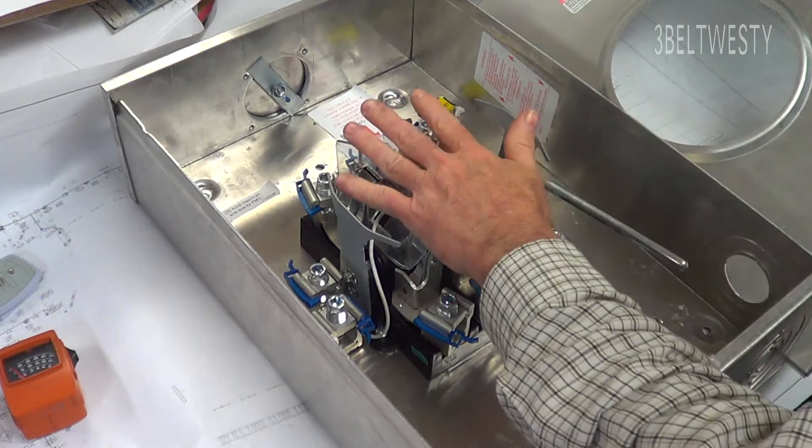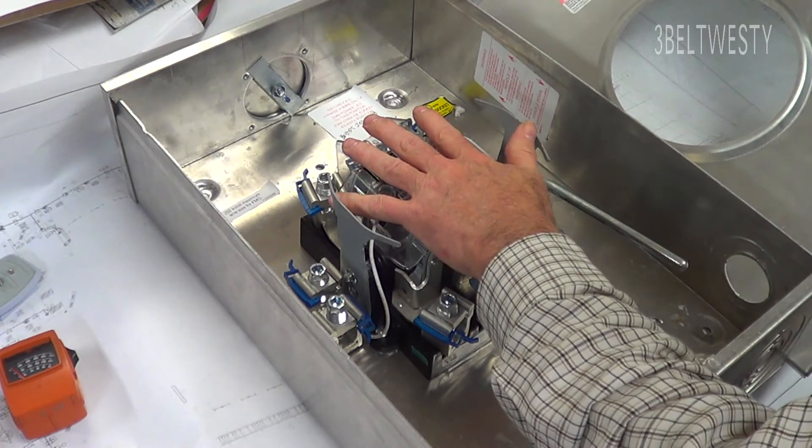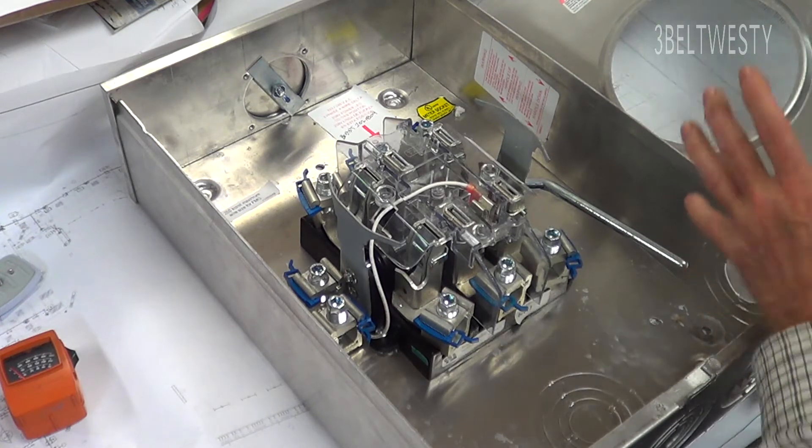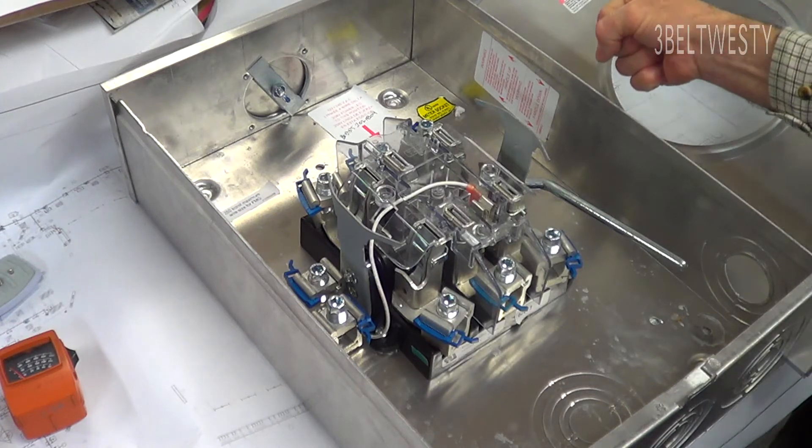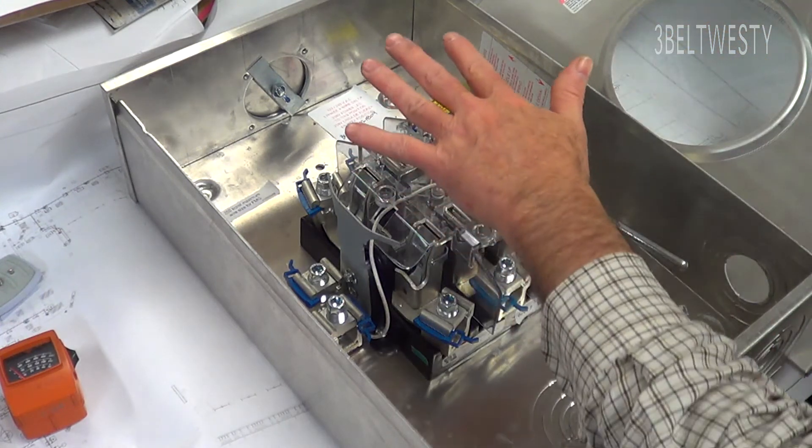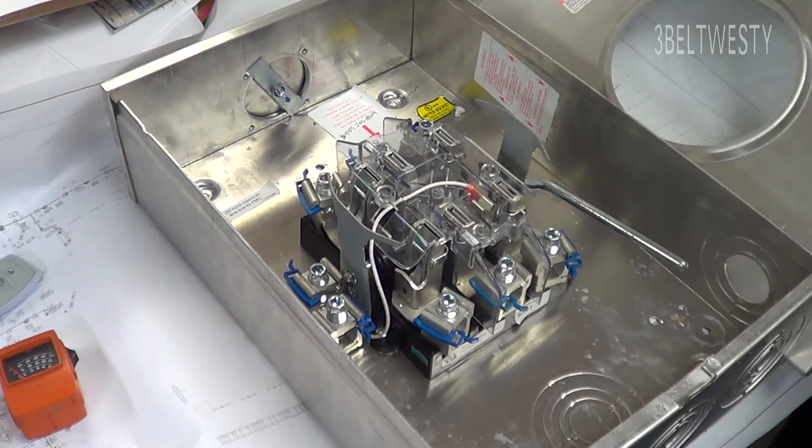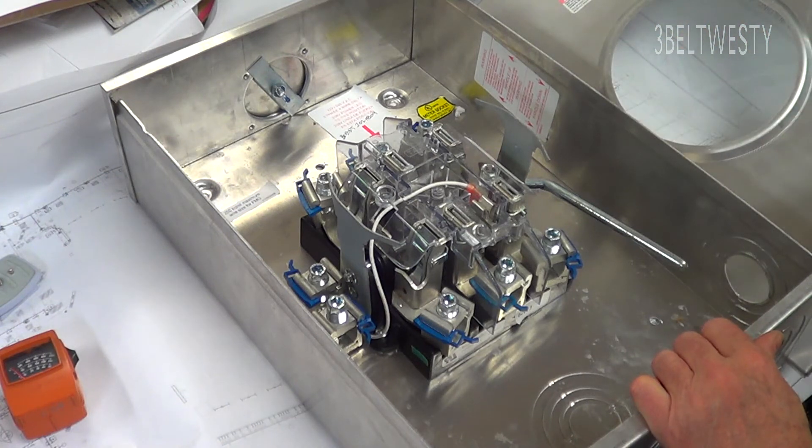Now in this locality, in the deep South here, if this is used for 480 volts/277, they want the output of this to go to a load disconnect that you can switch off - another box directly after the meter. They want to have something they can turn off directly after the output of this meter socket before the other stuff, other breakers, just so they have basically a main disconnect, probably for fire or something.